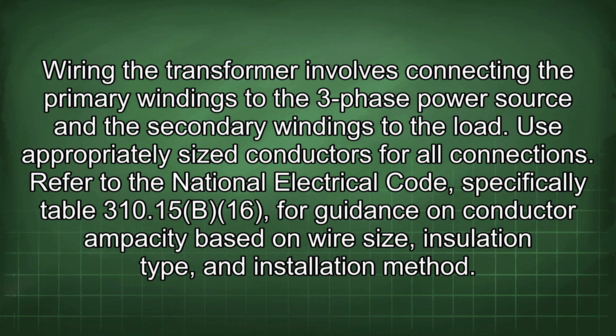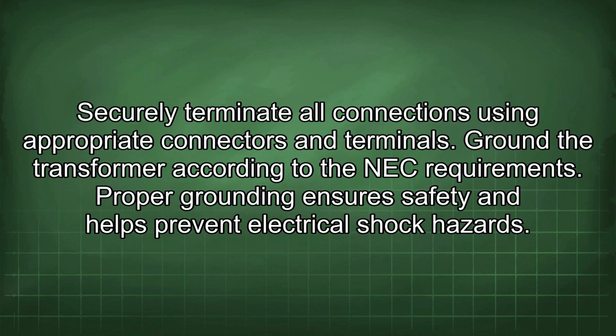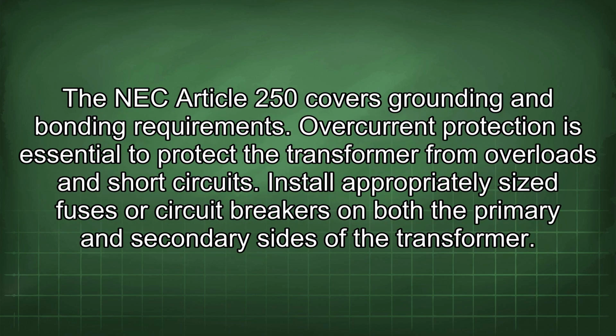Refer to the National Electrical Code, specifically Table 310.15(B)(16), for guidance on conductor ampacity based on wire size, insulation type, and installation method. Securely terminate all connections using appropriate connectors and terminals. Ground the transformer according to the NEC requirements. Proper grounding ensures safety and helps prevent electrical shock hazards. The NEC Article 250 covers grounding and bonding requirements.